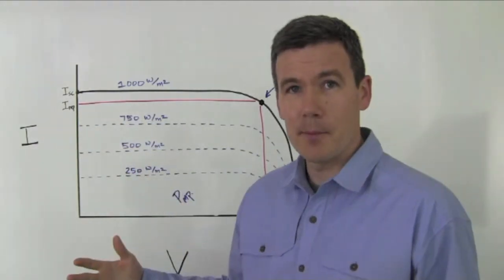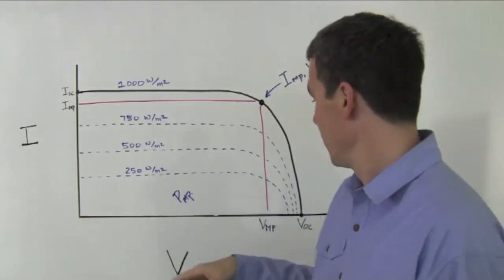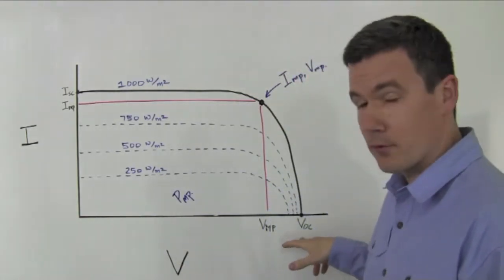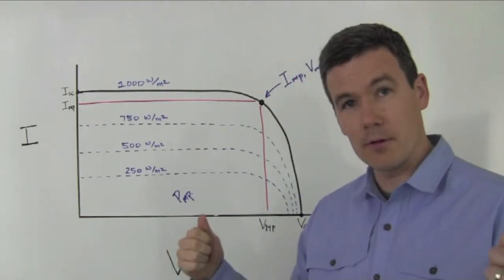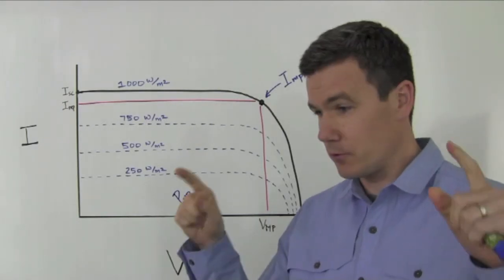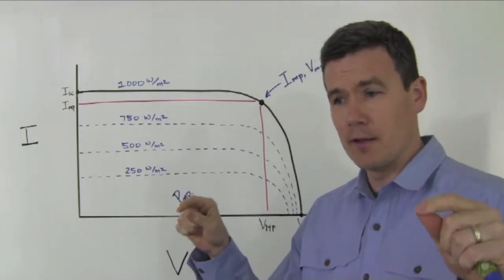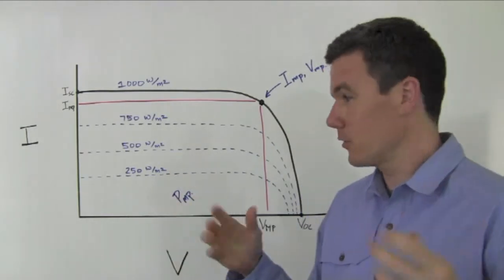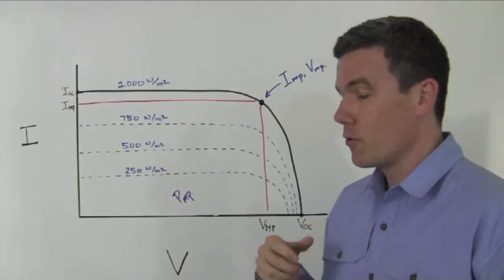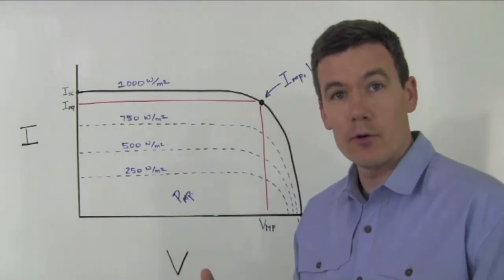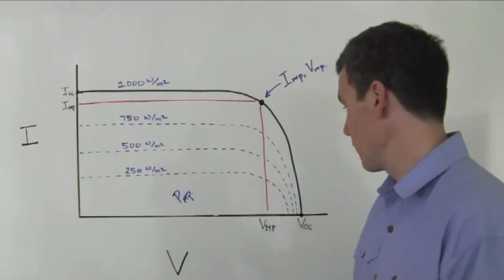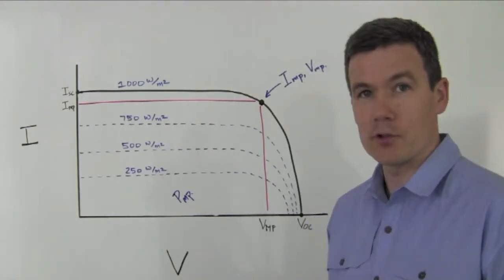IMP is the maximum current at maximum power. VOC is open circuit voltage. If you open circuit the ends of the lead of the solar module and place a meter there and measure the open circuit voltage, that's the open circuit voltage. That's the voltage that you measure at open circuit with no load pulling down the voltage on that solar module. And VMP is the voltage at maximum power.